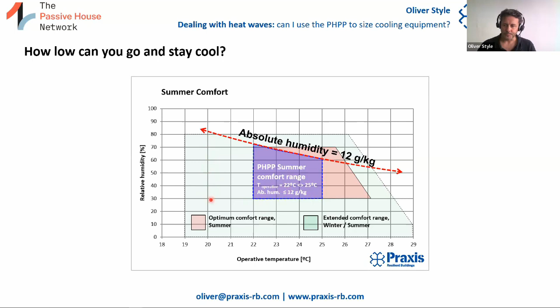And this is a graph that shows how not to do it. This is some of our experience in these kinds of projects, early projects, and the one I was mentioning, where we used the PHPP cooling loads just as they came off the PHPP for the certification. And here you can see monitored data in the main bedroom in a heat wave in July 2019, looking at air temperature and relative humidity. So this isn't operative temperature, because operative temperature is quite difficult to measure. It's the average of the air and mean radiant temperature.